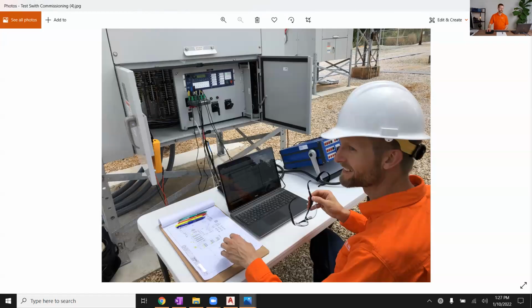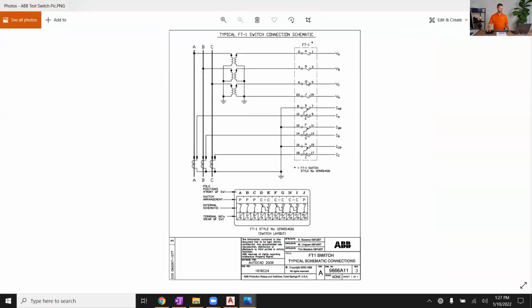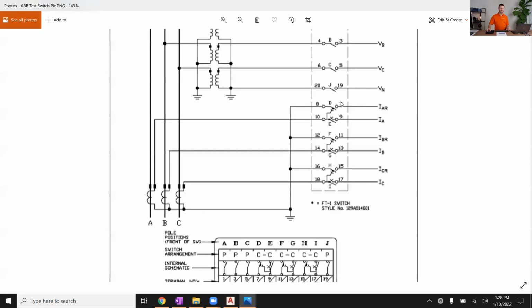So that's kind of the intent of a test switch. One other picture that might help shine a little light on that. ABB FT1 test switch. This is a little different configuration, but you see your CTs and PTs wired to the even side, the field side, and then the odd side is wired to the back of your relay, your voltage and current terminals, current in and current out, polarity dot and non-polarity dot.